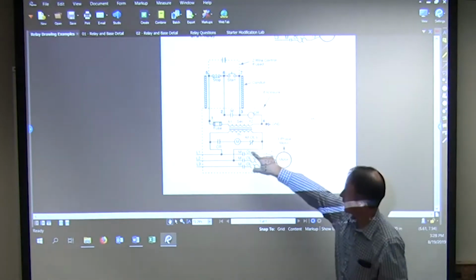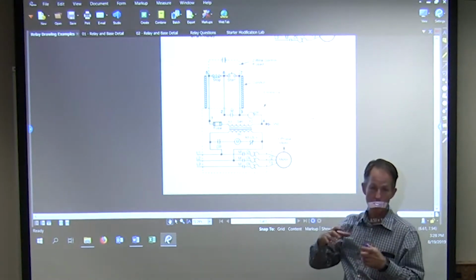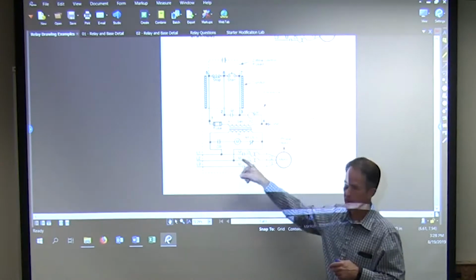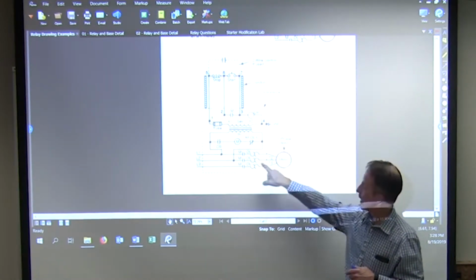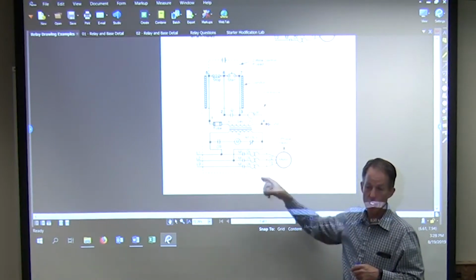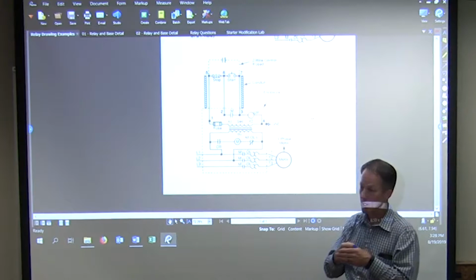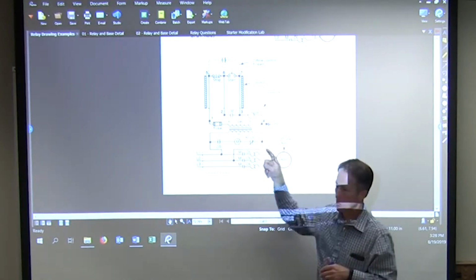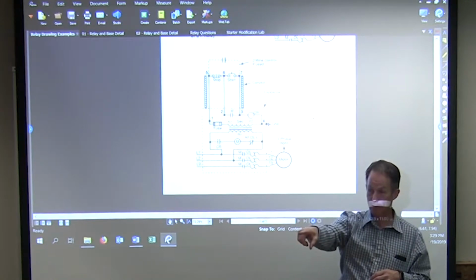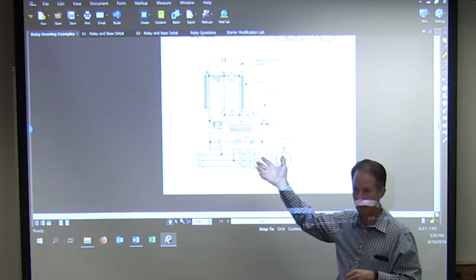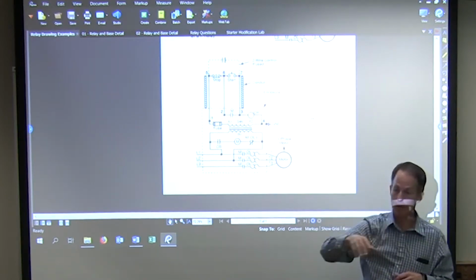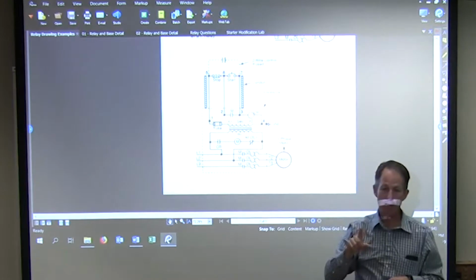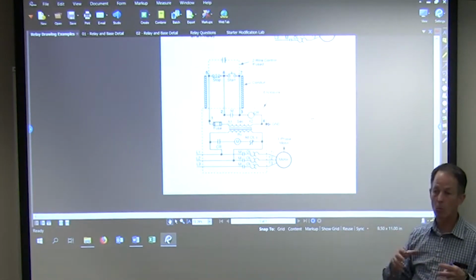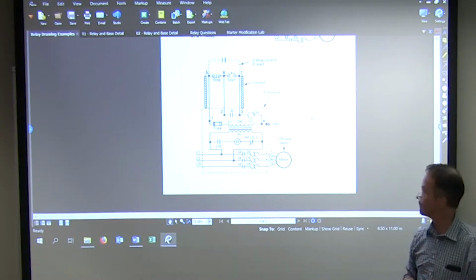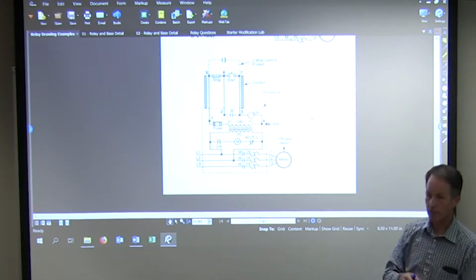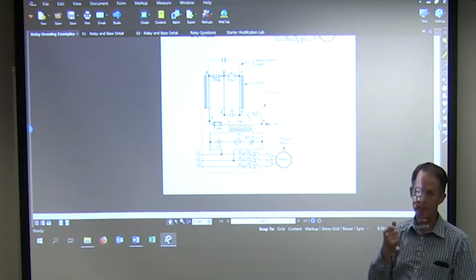And it was because this can be a very big coil, right? Because if this motor is a 50 or 100 horse motor, how big are these contacts? They're big. So it's going to take a lot of power to pull that silver in. This transformer may be bigger, so it could be up to 5 amps if it's a big transformer. But typically you're probably at half an amp, 1 amp for the control circuit. But you have to be careful, because the bigger you get, the more you'll need a bigger fuse in there. It's all based upon that, because there is an inrush, because you've got that delay on any type of inductive load.